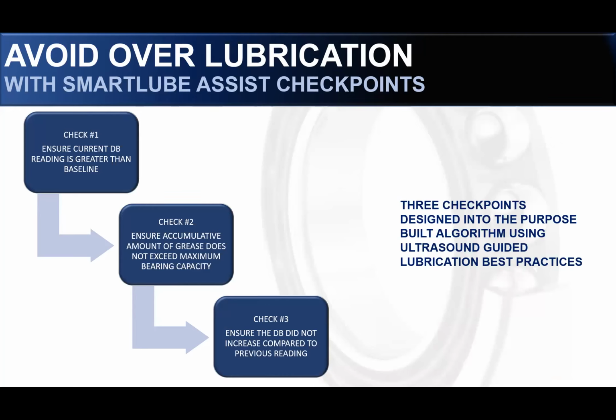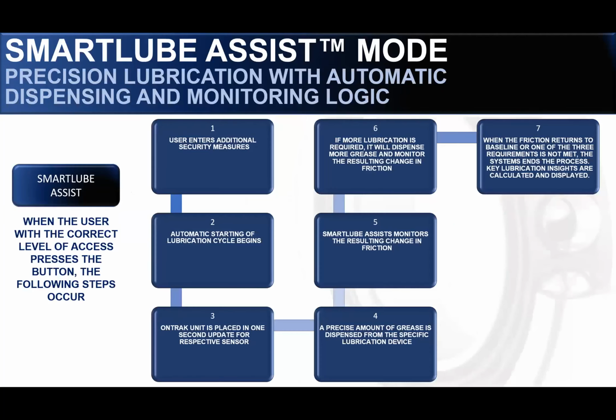There are times when we can never get it back to baseline because of known defects in the bearing, and we start to see that decibel increase. We didn't get it to go to baseline, but it starts increasing, indicating we're starting to fill that cavity. It is going to stop there. It's going to say, I tried to get it down to baseline. I couldn't. I got as close as I can. Then I started going up, so I stopped there. What's going to happen is you're going to receive a notification: this bearing requires lubrication.